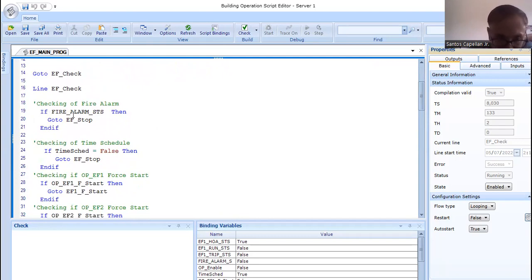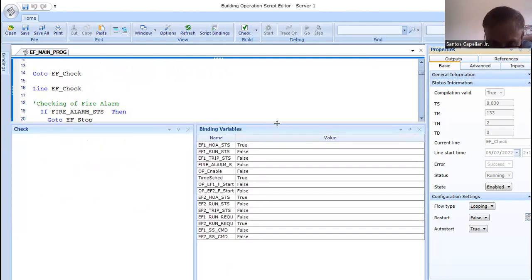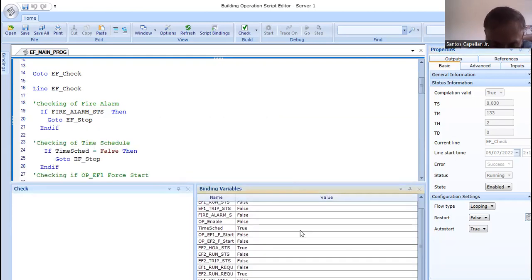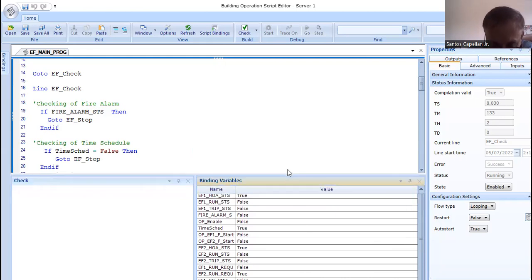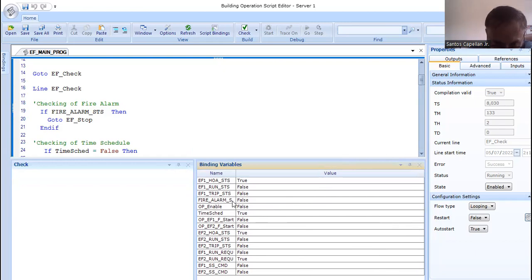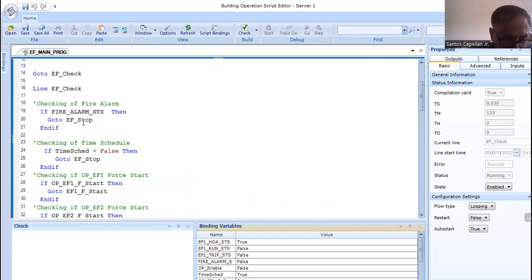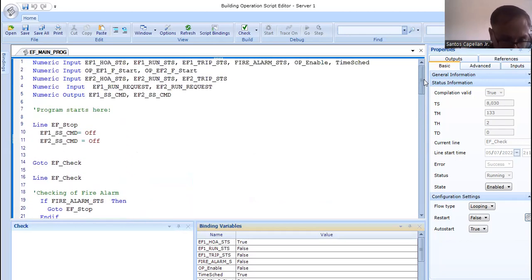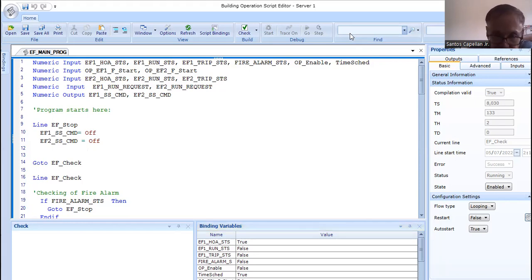At line 19, I check for fire alarm. If fire alarm is true, the program goes to EF Stop at line 20. The instruction there turns off EF1 and EF2 — the start/stop command is set to off. Then the program jumps back to EF Check and repeats.